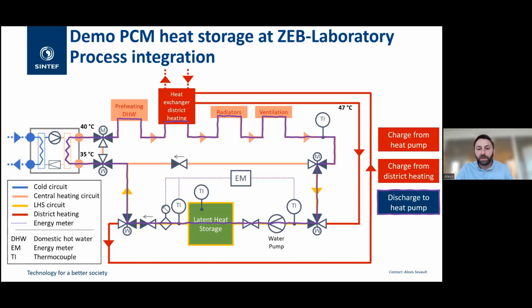On the return side, we circulate the water - let's say it goes back at 30 degrees - through the latent heat storage, which was preloaded above 37 degrees. The water comes out warmer than 30 degrees, most likely around 35 degrees, and then runs back to the heat pump. This supports the work of the heat pump - we consume less electricity while still delivering heat at 40 degrees to the building. That's how we support operation on very cold days, doing peak shaving in that case.